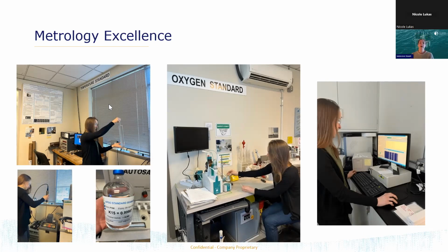And we have a regular program of sending benchmarking units between our labs. So we have multiple labs throughout our buildings in Bellevue, and then we have our primary calibration facility in Kempten, Germany. And we will send instruments back and forth between those sites, those baths, those rooms, to make sure that every bath is working the way that we anticipate. The goal is that you as a customer shouldn't be able to tell where your instrument was calibrated. It should be the same truth regardless of where that's happening.